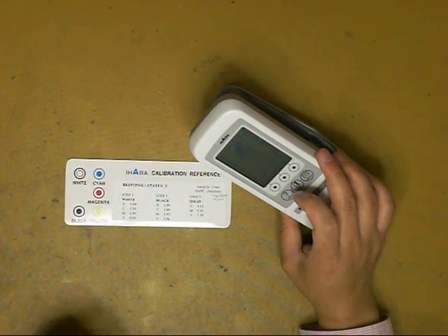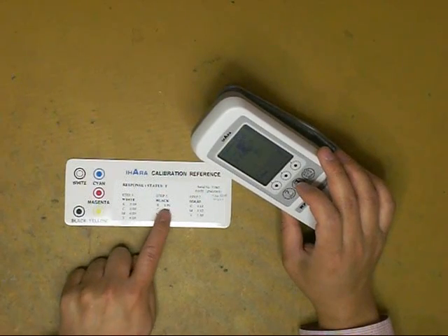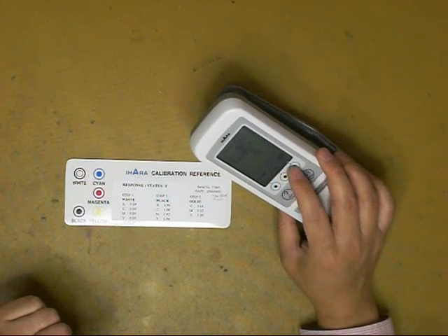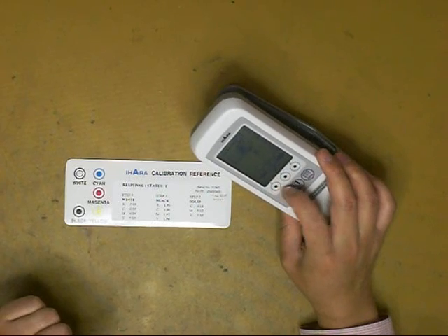Step two: input calibration value for the black patch. The first value is 1.90. The instrument indicates 1.76. Press edit, adjust the value to 1.90, and hit enter.